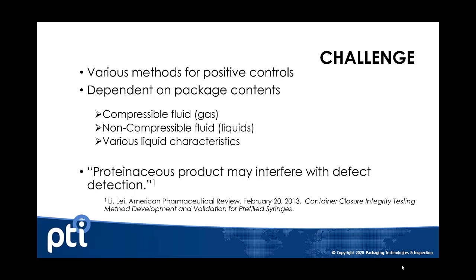The type of positive control that you use is very important. As it relates to the container type, the product that's in that container will definitely impact how that positive control performs and how it impacts the results that you produce. In the pharmaceutical space, especially with parenterals, this is very critical because we're looking for small defects. But for certain class products such as biologics, the risk of that product actually plugging a defect is quite great.